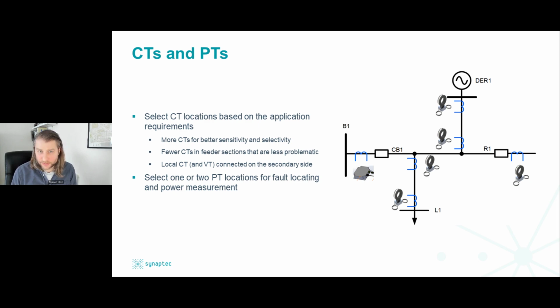With that fiber infrastructure in place, sensors can be readily deployed wherever it's useful. And the Synaptec approach, which Neil has explained, can be used to connect to existing CTs. So we can connect to the secondary of existing sensors that are already deployed, pole mounted or otherwise. But if they don't exist, we can also readily supply CTs that can be fitted and connected to the fiber also. And by selectively adding voltage sensing at some strategic locations, you can get distribution fault location capability with quite good accuracy, which we'd expect to be around about 5%. That basically immediately becomes possible through this approach.